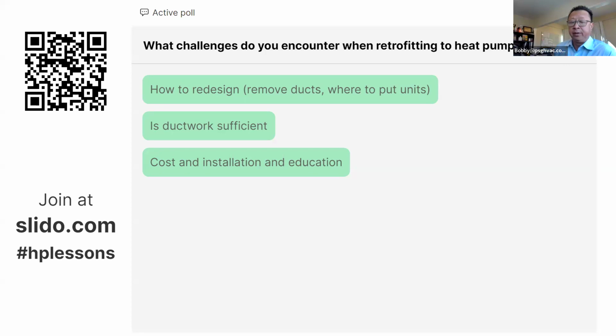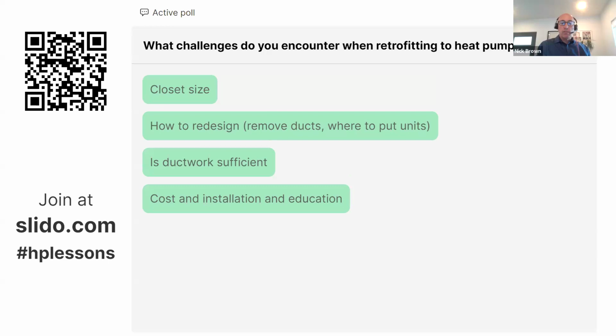That brings up another conversation, where these variable capacity heat pumps come in a furnace style configuration. That's a new one, because most people think about ductless or ducted units, but really there are mini splits that have ducts too. There are all kinds of different new units with different statics that can overcome that. So yes, you really want to take a look at your ductwork. Okay, redesign, including duct system, aesthetics for the heads of the mini splits.